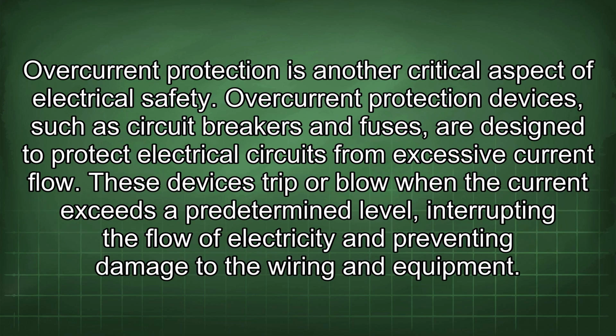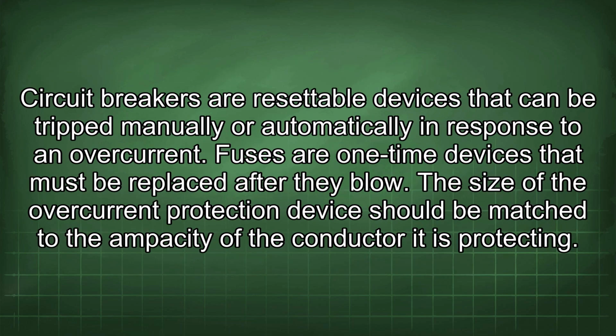Overcurrent protection is another critical aspect of electrical safety. Overcurrent protection devices, such as circuit breakers and fuses, are designed to protect electrical circuits from excessive current flow. These devices trip or blow when the current exceeds a predetermined level, interrupting the flow of electricity and preventing damage to the wiring and equipment. Circuit breakers are resettable devices that can be tripped manually or automatically in response to an overcurrent. Fuses are one-time devices that must be replaced after they blow. The size of the overcurrent protection device should be matched to the ampacity of the conductor it is protecting.